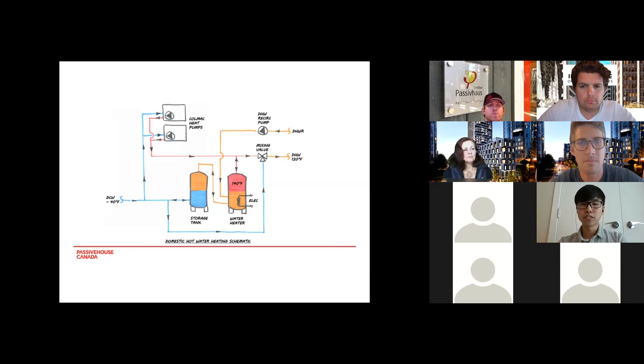The third point, as some of you may have noticed, is that I actually piped the domestic hot water through the tanks in series, for a few reasons. One was to increase the overall storage volume in the domestic hot water system—I treated the electric water heater as a secondary domestic hot water storage tank.